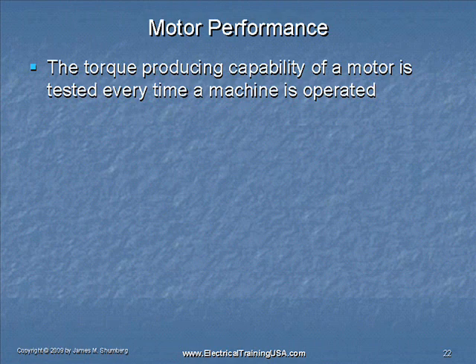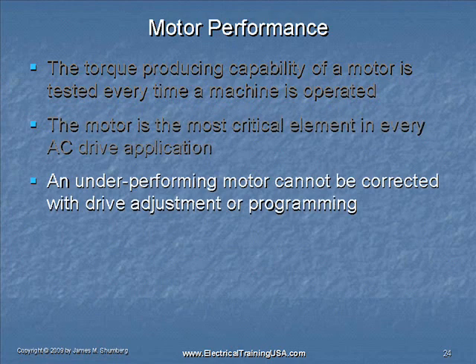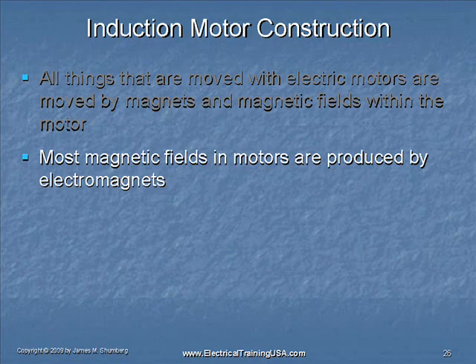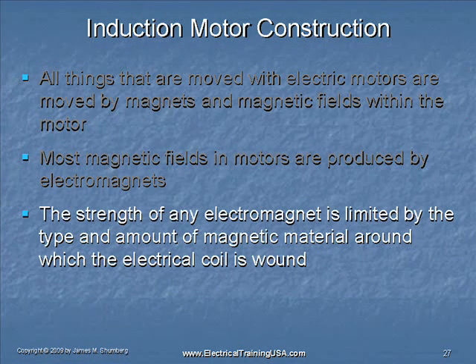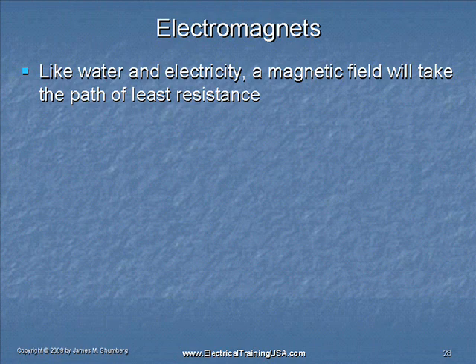The torque producing capability of a motor is tested every time a machine is operated. An underperforming motor cannot be corrected with drive adjustment or programming. All things that are moved with electric motors are moved by magnets and magnetic fields within the motor. Most magnetic fields in a motor are produced by electromagnets. The strength of any electromagnet is limited by the type and amount of magnetic material around which the electrical coil is wound. Like water and like electricity, a magnetic field will take the path of least resistance.